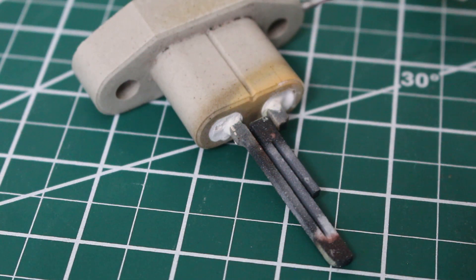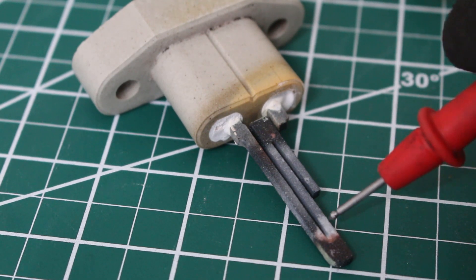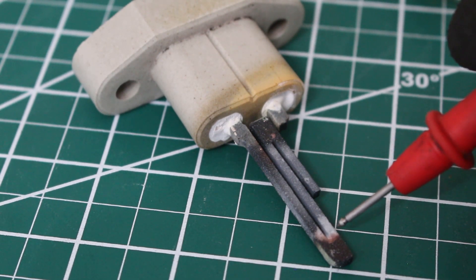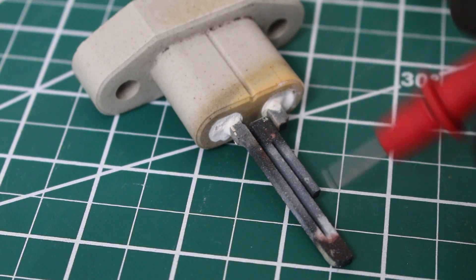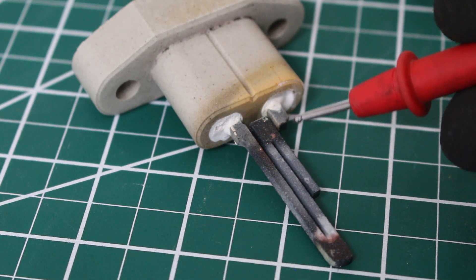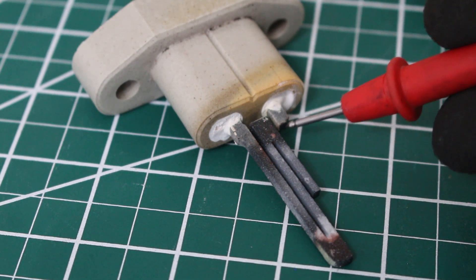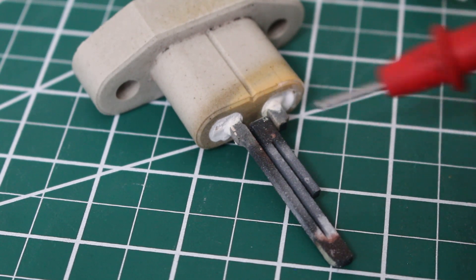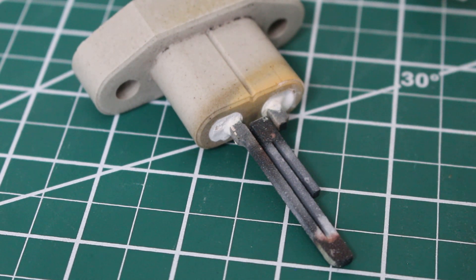If we look at the hot surface igniter itself we can see a white mark. That is a big indication that it is faulty and it is broken. But if you look closely here there is a break in this. And 100% this is a faulty hot surface igniter and it must be replaced.